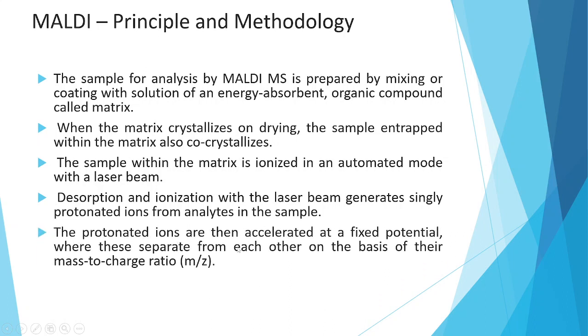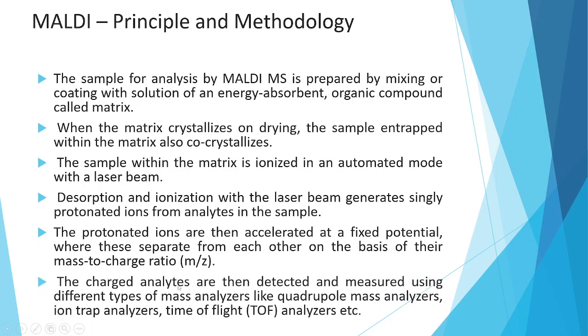Desorption and ionization with the laser beam generate singly protonated ions from analytes in the sample. The protonated ions are then accelerated at a fixed potential where they separate from each other on the basis of their mass-to-charge ratio. The charged analytes are detected and measured using different types of mass analyzers like quadrupole mass analyzers, ion trap analyzers, and time-of-flight analyzers. Here we are talking about time-of-flight analyzers.